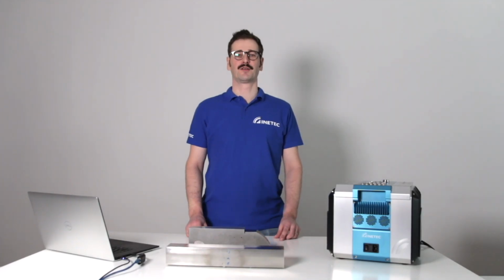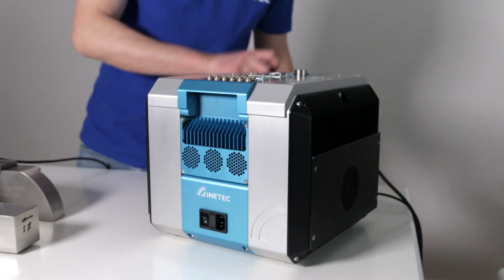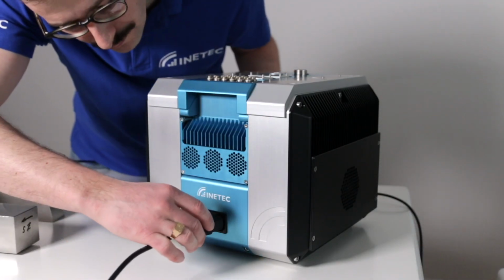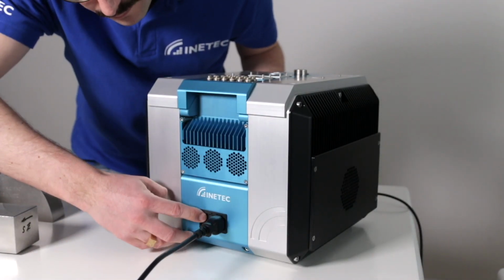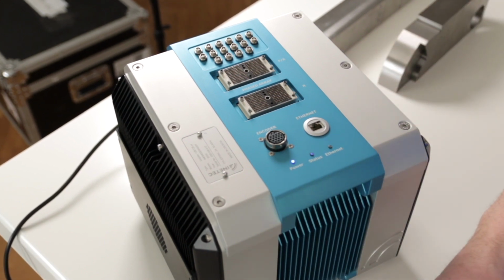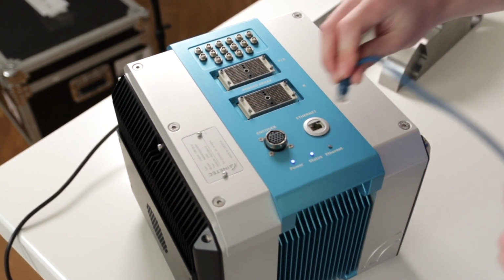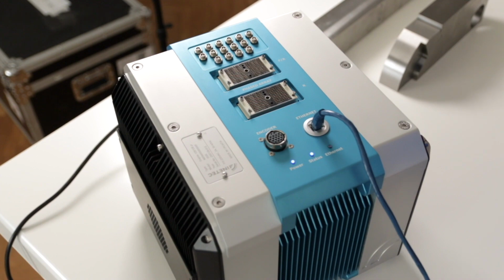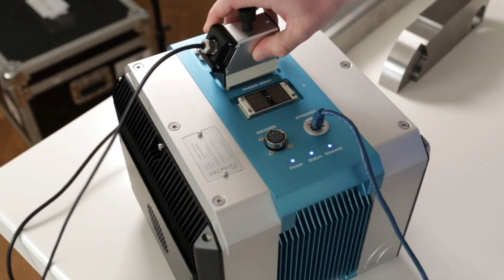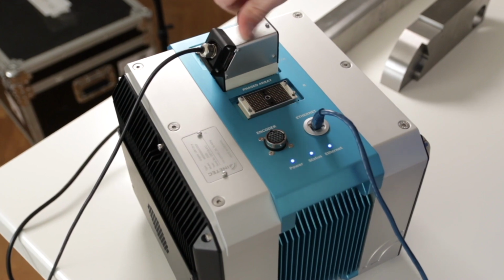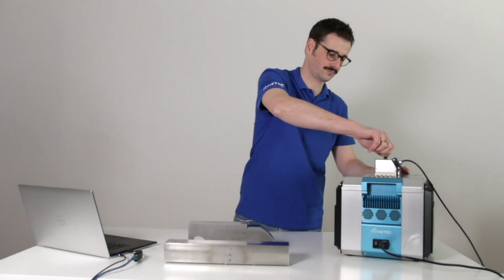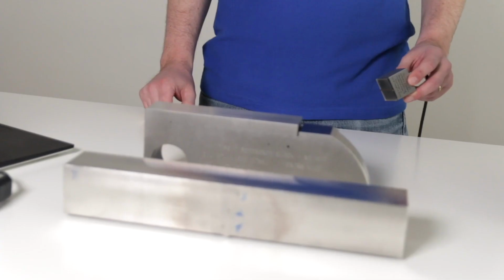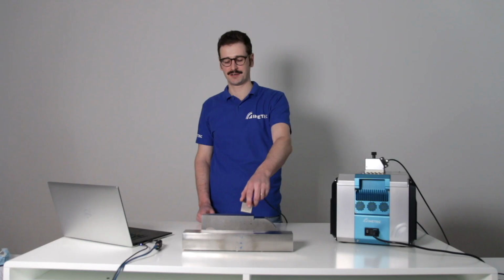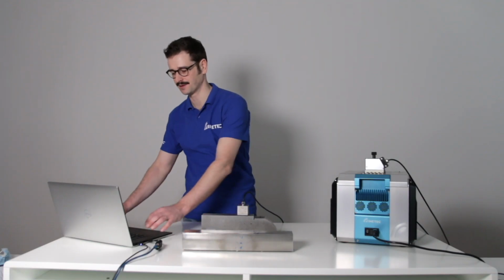Let me connect the Dolphin instrument. I will plug the power outlet, turn on the instrument, connect the Ethernet cable to the computer, and connect the probe via the hypertronic connector on top of the Dolphin instrument. I'll place the probe on the calibration block and I'll start the Signy1 software.